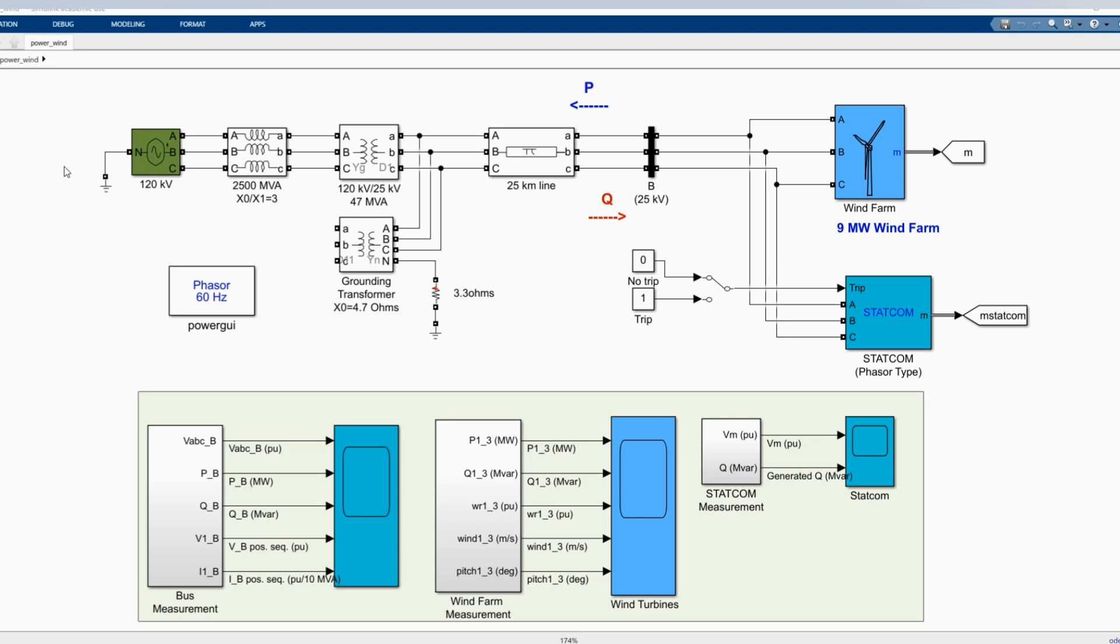Each wind turbine has a protection system monitoring voltage, current and machine speed. Reactive power absorbed by the induction generator is partially compensated by the capacitor bank connected at each wind turbine low voltage bus at 400 kVAR. The rest of reactive power required to maintain the 25 kilovolt voltage at the bus close to 1 per unit is provided by a 3 Mvar STATCOM with a 3% droop setting.